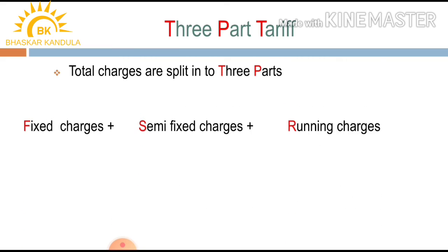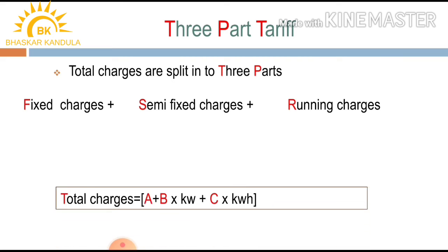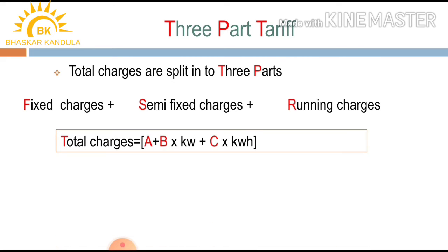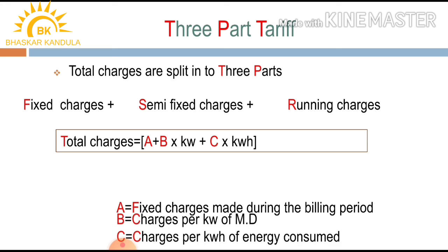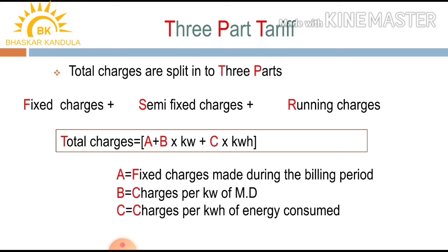In three-part tariff, the total charges are split into three parts: fixed charges, semi-fixed charges, and running charges. The expression is: total charges = a + b × kilowatt + c × kilowatt hour, where 'a' is the fixed charges during the billing period, 'b' is the charges per kilowatt of maximum demand, and 'c' is the charges per kilowatt hour of energy consumed.